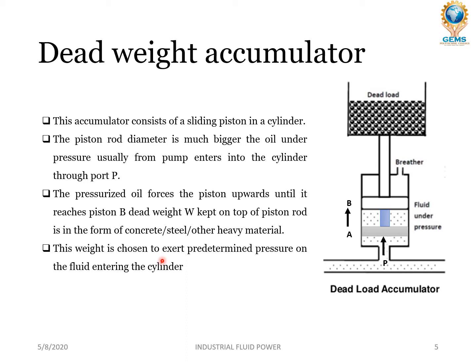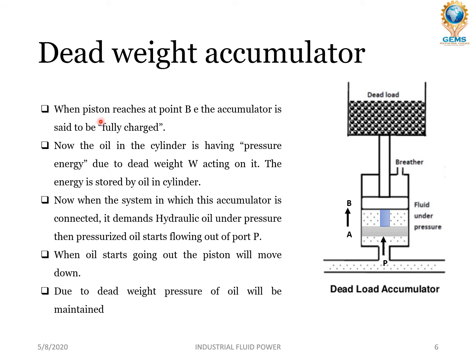This weight is chosen to exert a pre-determined pressure on the fluid entering the cylinder. According to the pre-determined pressure needed, the load is calculated and kept on the piston rod. When high pressure fluid comes in, it forces the piston to move up, from position A to position B. When the piston reaches point B, the accumulator is said to be fully charged.